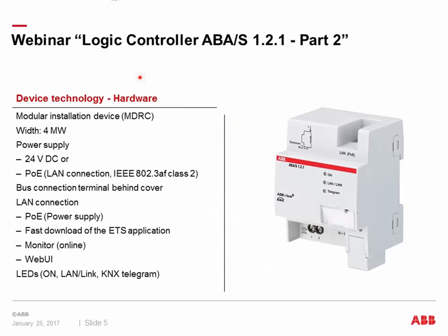Now let's come to some hardware information of the device. It is a modular DIN rail component. The module width here is 4 modules. Very important, the device needs an additional power supply. It can be a 24 volt DC power supply or it can also be supplied via PoE, via the IP connection, or both together at the same time. But be careful when you use PoE, you have to follow the standard, an IEEE 802.3af class 2 device.